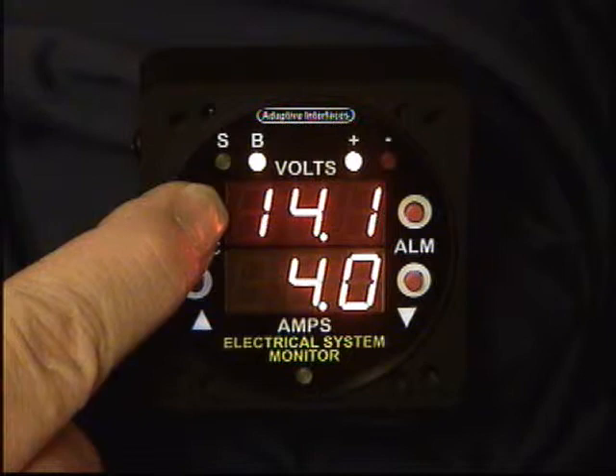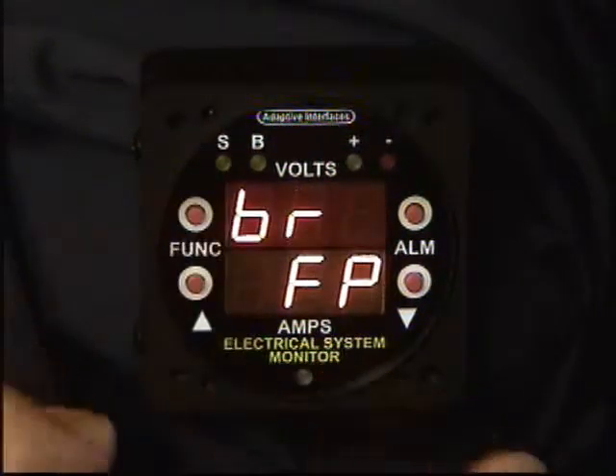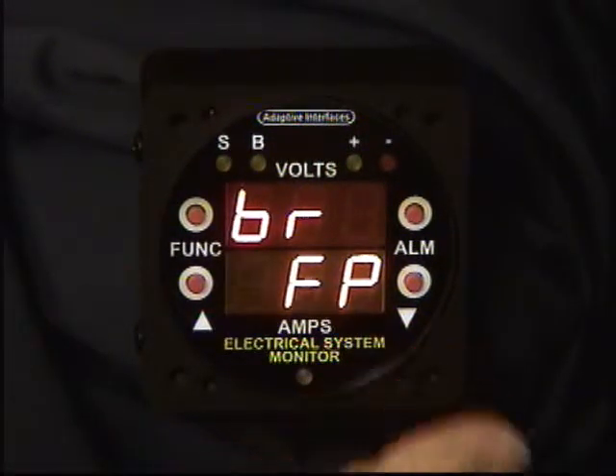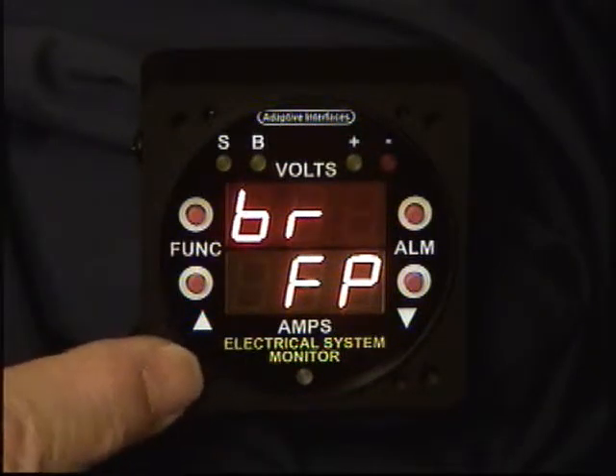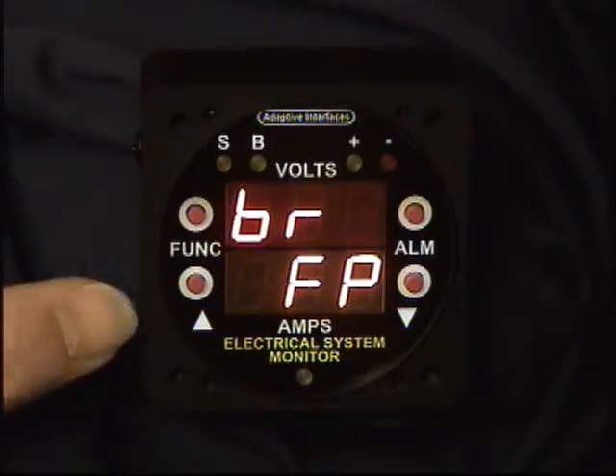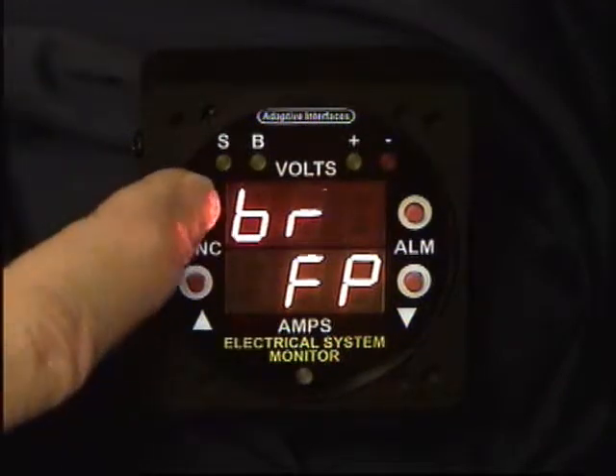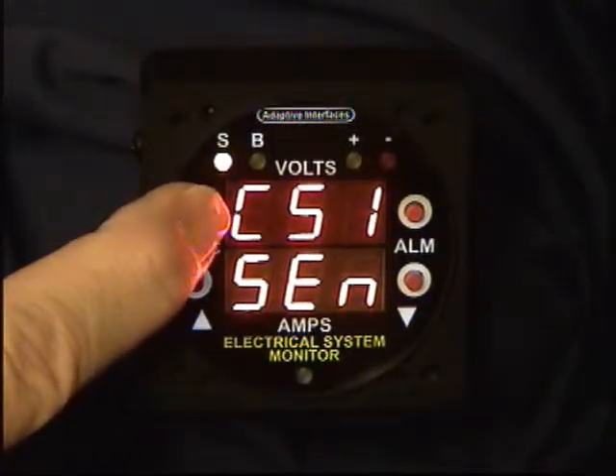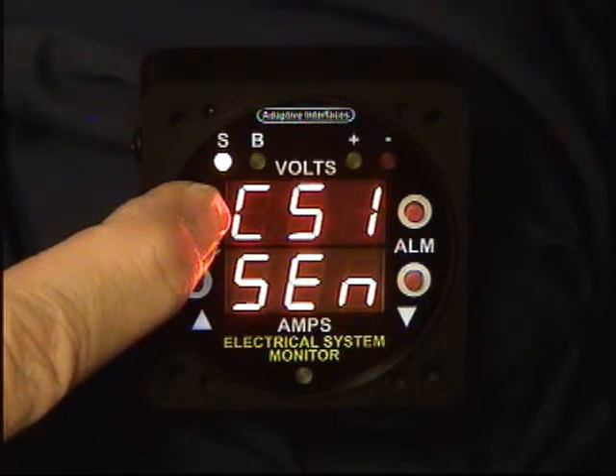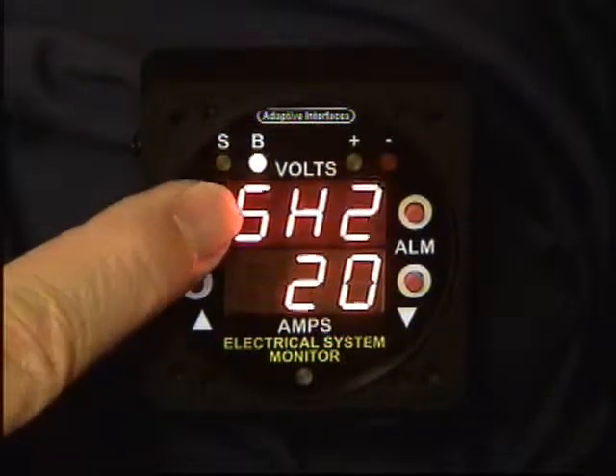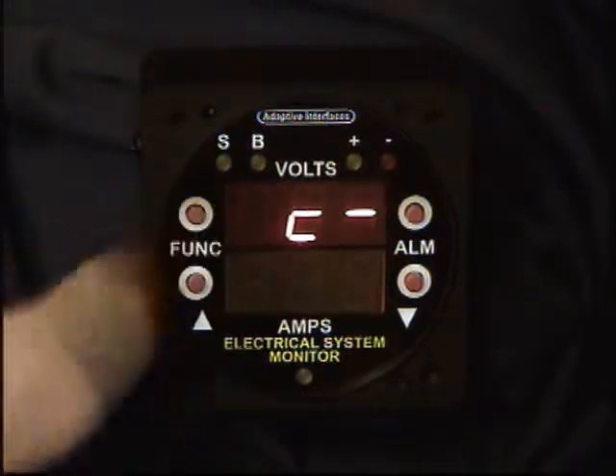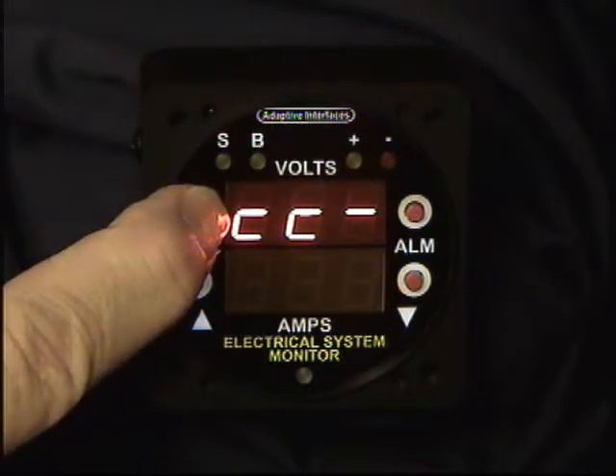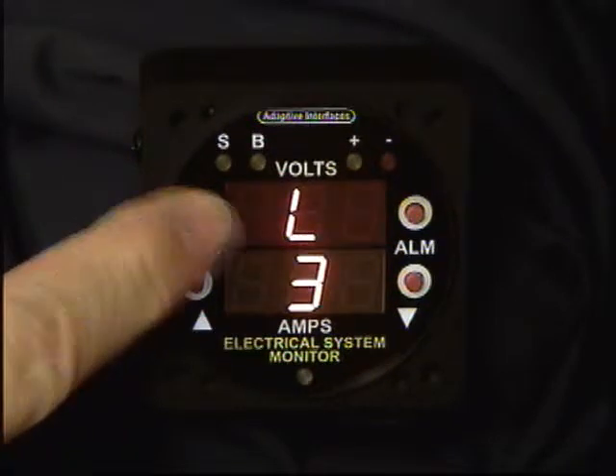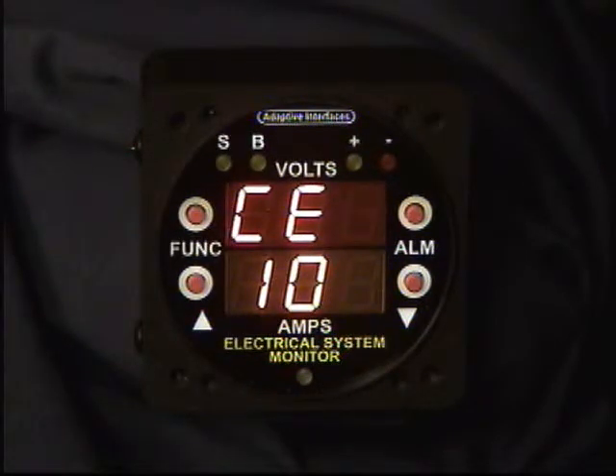And this is a level that we don't encourage anybody other than a trained technician to use, because what you're going to be doing is setting up the calibration of the instrument. Right now we're in menu level 1. Let's press the function button and hold it in for 5 seconds. We're in level 2. These are the functions we just went over. Press and hold the function button again. We are now in level 3. And this is the menu that allows you to enter calibration data points for the instrument.